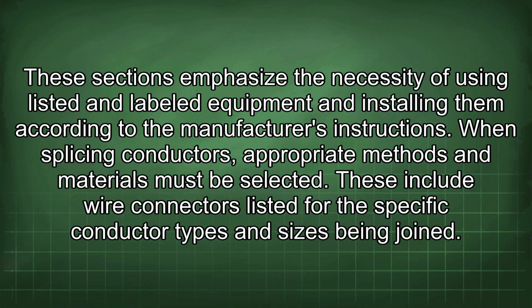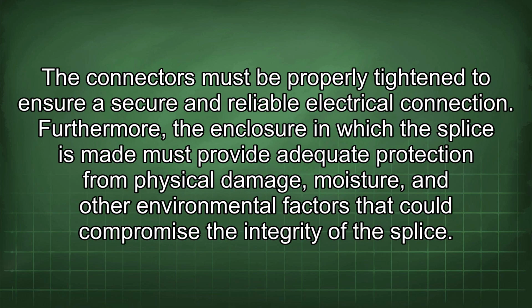When splicing conductors, appropriate methods and materials must be selected. These include wire connectors listed for the specific conductor types and sizes being joined. The connectors must be properly tightened to ensure a secure and reliable electrical connection. Furthermore, the enclosure in which the splice is made must provide adequate protection from physical damage, moisture, and other environmental factors that could compromise the integrity of the splice.